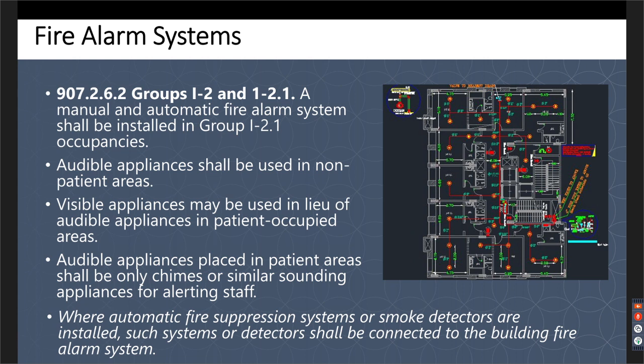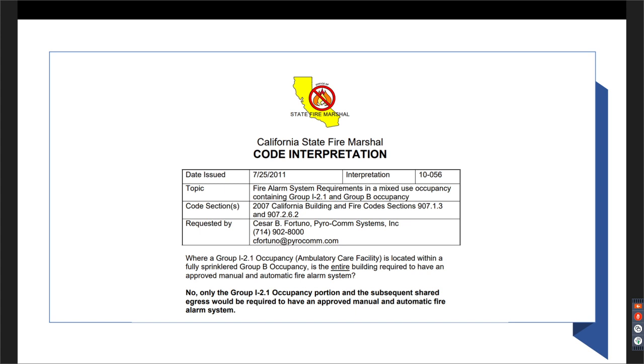Now here's a question, a formal code interpretation from the State Fire Marshal's office that is interesting because earlier we mentioned that sprinklers have to be installed throughout the building. What about fire alarm? The question says, where I have a group I-2.1 ambulatory care facility located within a fully sprinklered B occupancy, is the entire building required to have an approved manual and automatic fire alarm system? And the answer from SFM is no. Only the I-2.1 portion and the shared egress would be required to have this fire alarm system installed.